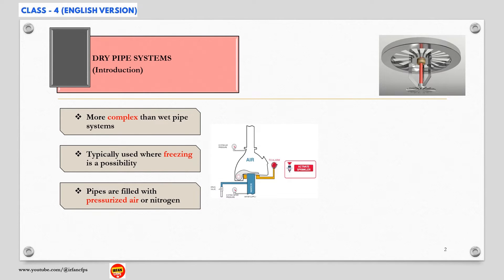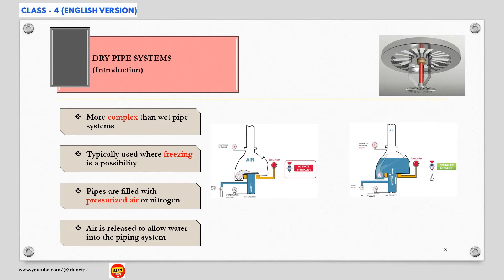Dry systems also employ automatic sprinklers. As you can see from the figure shown on your screen, these systems do not contain any water in the piping network above the dry type valve to avoid freezing. In this type, the pipes are filled with pressurized air or nitrogen above the dry type valve. Upon activation of sprinkler system, air is released and water flows through the piping network connected to the water supply.